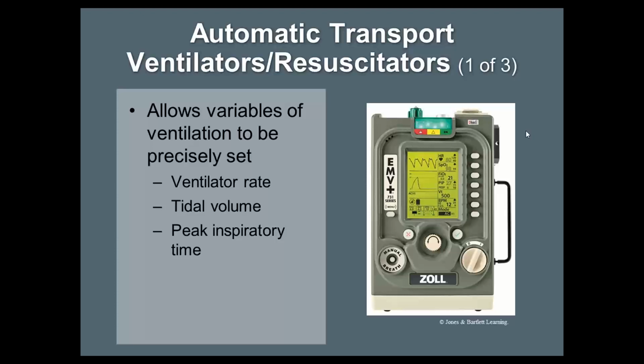Now, underneath that, you'll see something called PIP, which is peak inspiratory pressure. And they usually want to top that off at around 30 millimeters of mercury. 30 to 35 is on the top end of that. So this person is doing about 27. That's what their pressure is in there, and that may be what their normal airway pressure is, what they're being resistant on. That's the amount of pressure that vent is pumping air against inside the lungs.